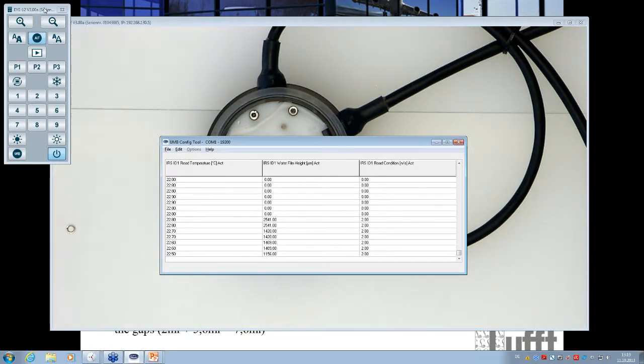And you see, now we have a changed value for the water film. So it's about 1142. Normally it should be 1000. Of course, I have done it now very fast. I have not really checked the 7.6. Maybe it was a little bit too much. But of course, if you are in front of the station, you can do that more accurately than I have done it now. But you see, it's around this value. So you will get a value around 1000 micrometers.